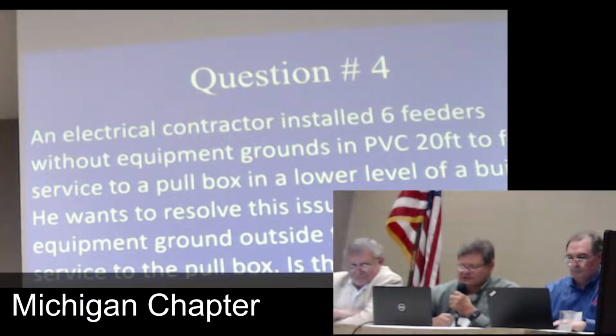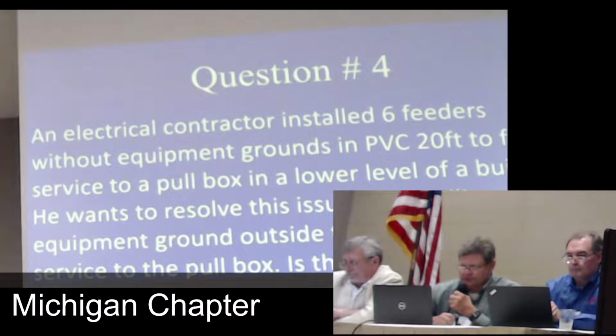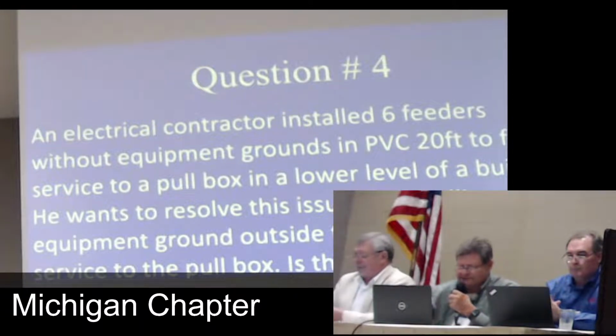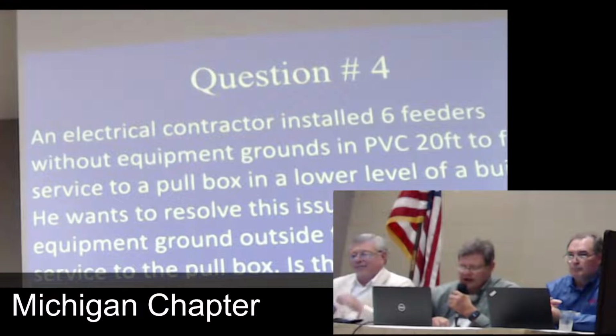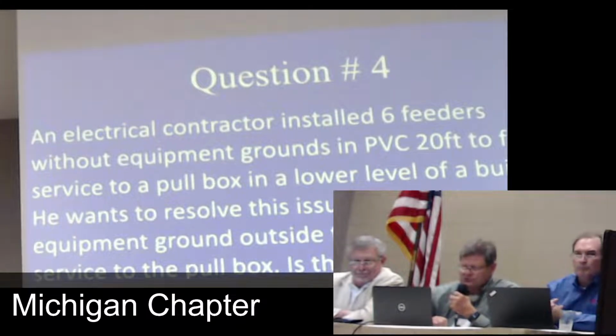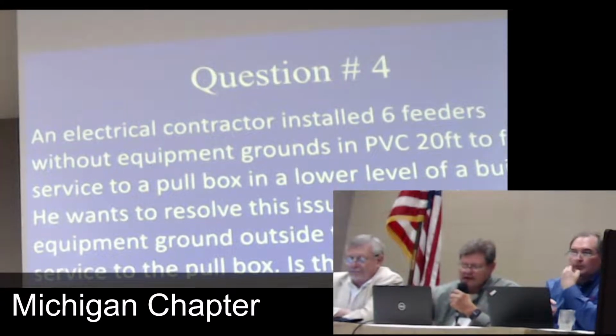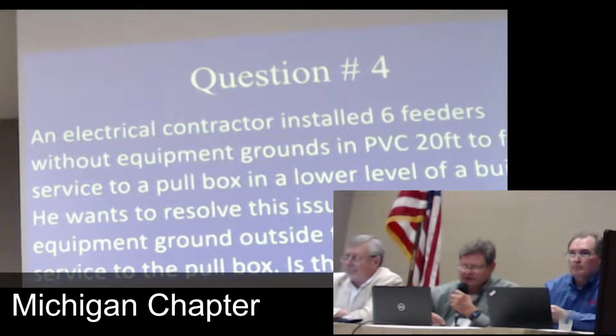And a couple of code sections to look at here, 300.3(B), which is conductors of the same circuit, states that all conductors of the same circuit, and where used, the grounded conductor and all equipment grounding conductors and bonding conductors shall be contained within the same raceway, auxiliary gutter, cable tray, etc., etc. 2 other sections to look at would be 250.120(A) and also 250.102(E)(2), which states bonding jumpers are allowed so that you can install that conductor on the outside. However, 250.102(E)(2) limits that to a length of 6 feet. So the installation would be non-compliant.